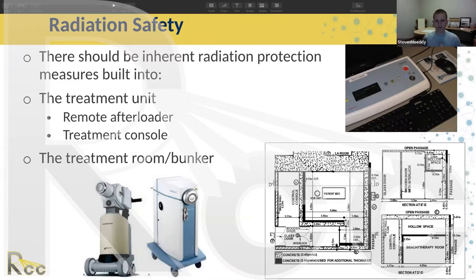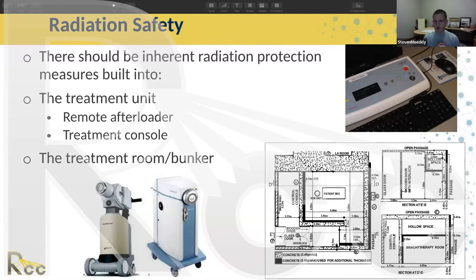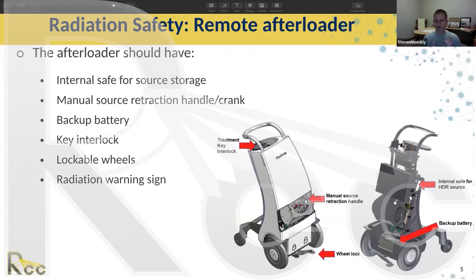You should have a door interlock that won't allow you to treat when it's open. The console should have interlocks. In the United States, we have an interlock that allows only one type of radiation-producing device at a time. The afterloader should have an internal safe for storage, a manual source retraction mechanism — you should be trained thoroughly on how to use that manual source retraction handle in case the source is out and stuck.